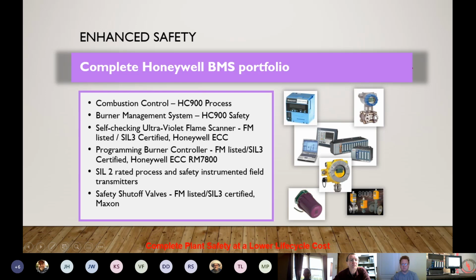Smart transmitter, so obviously pressure, flow, level, whatever you're trying to sense. Honeywell has a full line of smart transmitters to accommodate you there. Right in the middle, this yellow sensor is the Honeywell Analytics sensor that I was talking about earlier, where we were monitoring O2 and some of the other LEL type applications where we want to use the HC900 as a personal safety or environmental safety type device. These sensors can be placed out on the plant floor and sense those different gases or O2 or CO or whatever it is, and bring that back into the HC900 with either a Modbus connection or a 4 to 20 milliamp.